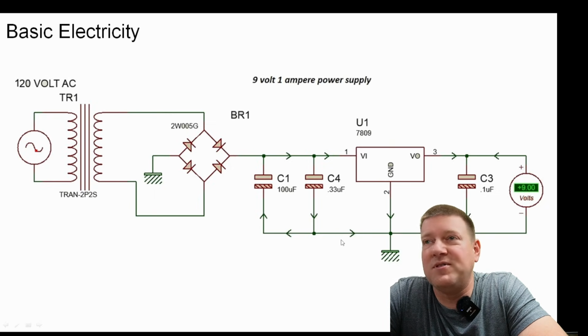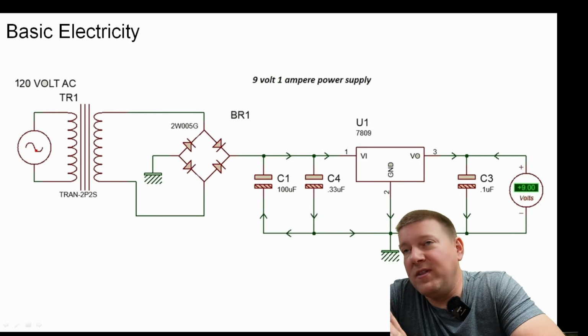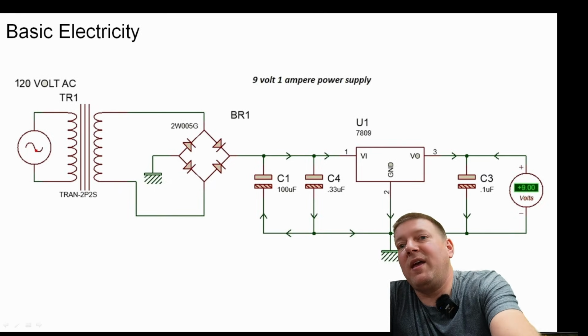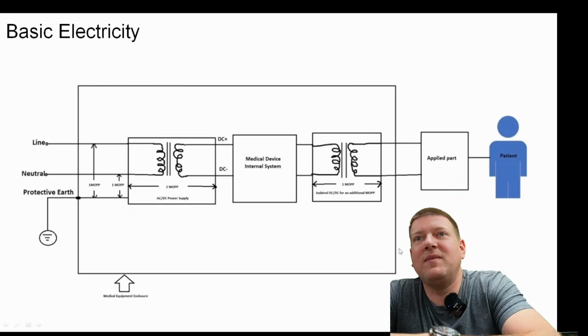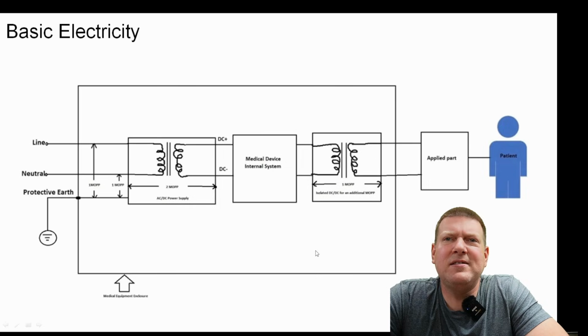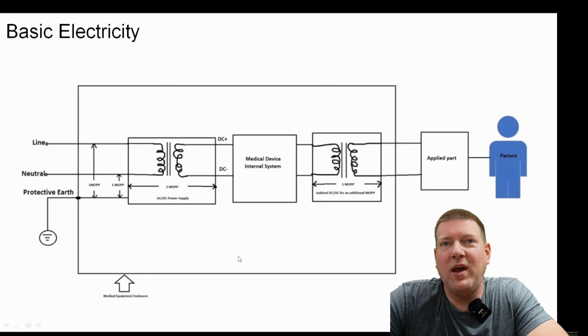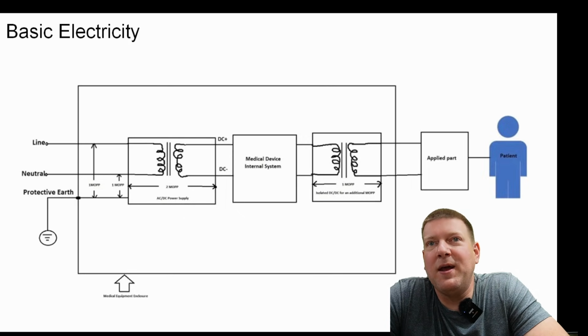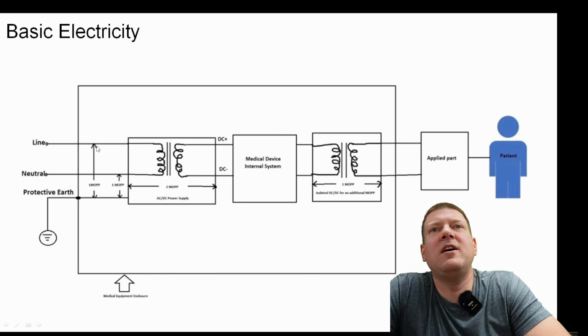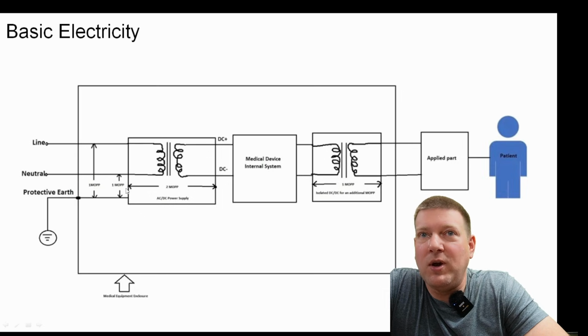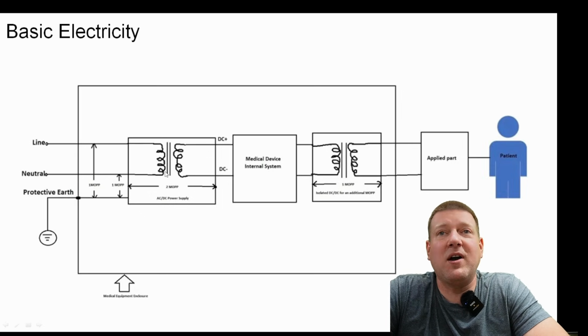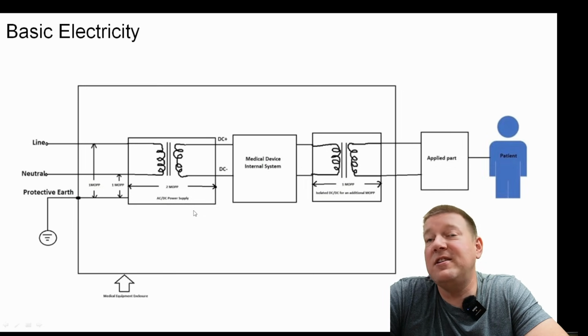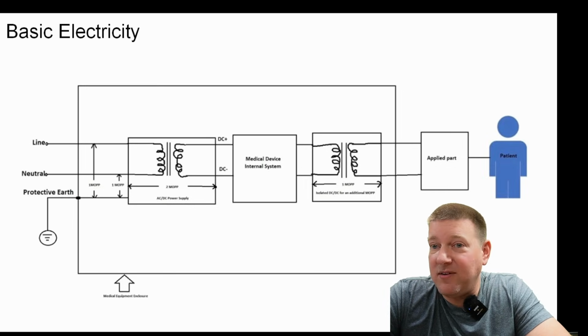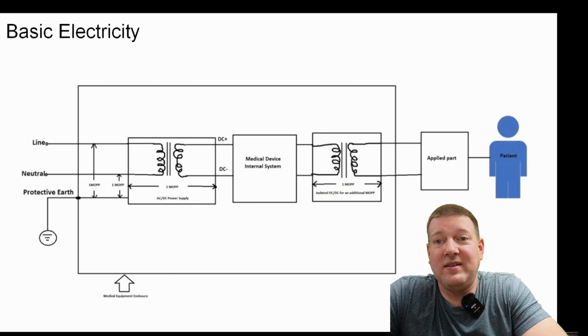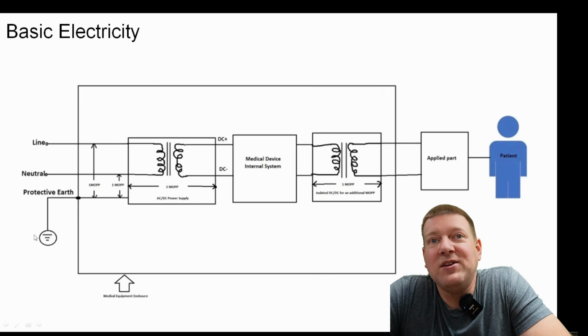And this is just a 9-volt simple power supply. Not very efficient whatsoever. This is not a medical grade power supply, and we'll talk about that in just a moment. Big difference. So this is probably the closest I can come to a diagram of what a medical power supply is. It might be crude, but whoever did this, good on you, because this really gets the point across. So right here we have the line in neutral, and you can see that same transformer that I was talking about. And the chassis of this device, the outside of it, is going to be ground. Remember, a lot of medical devices, the metal housing is grounded, right? You can see that right here.